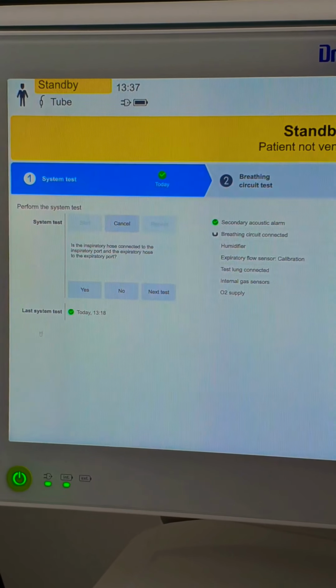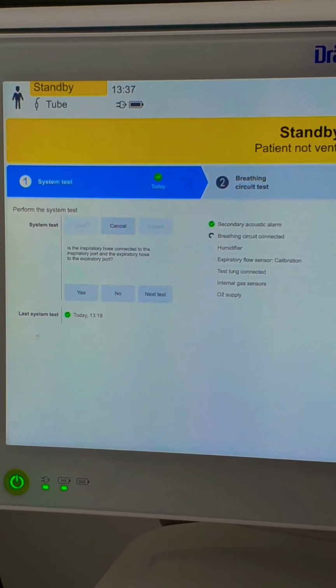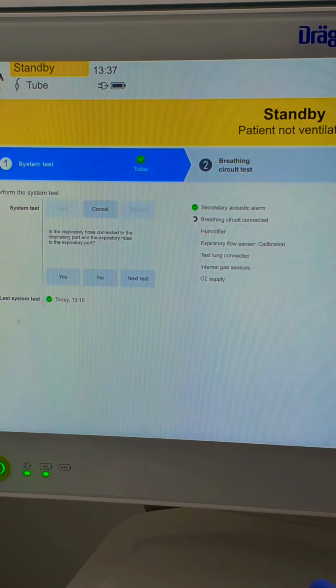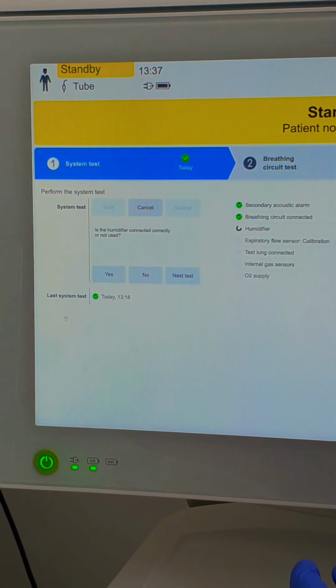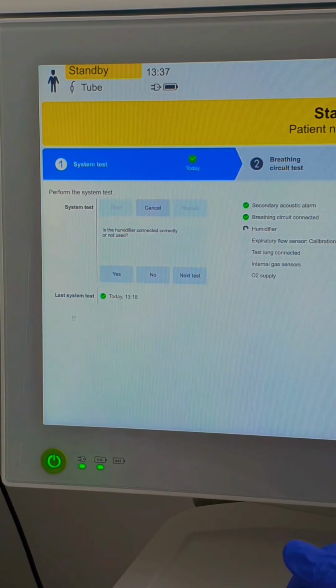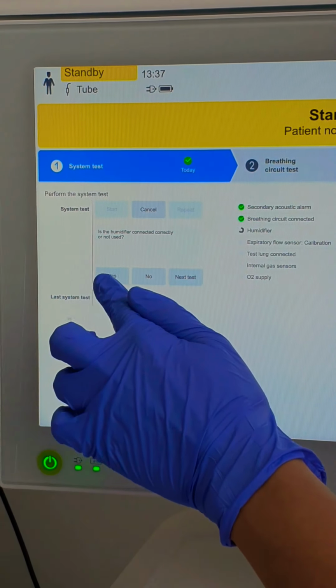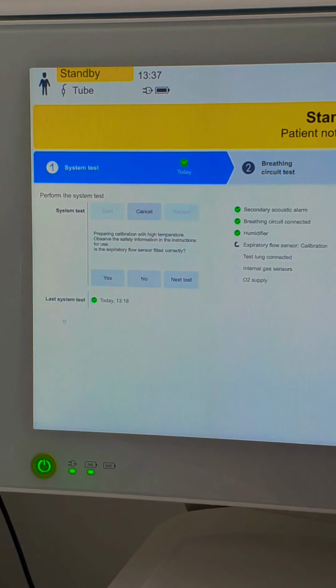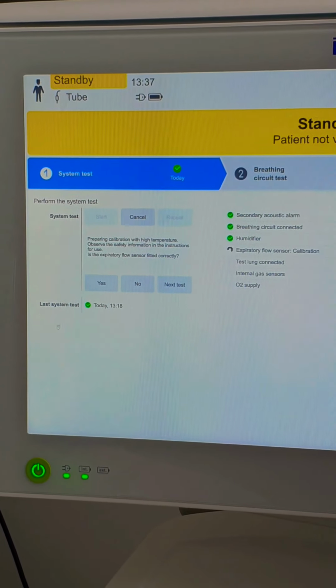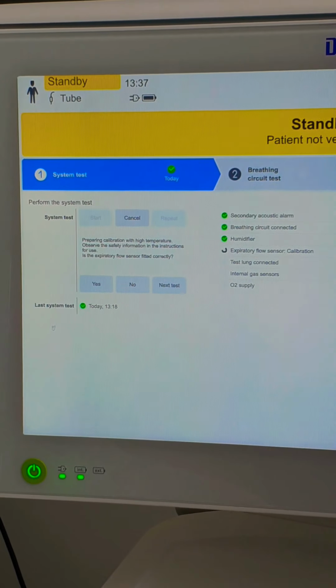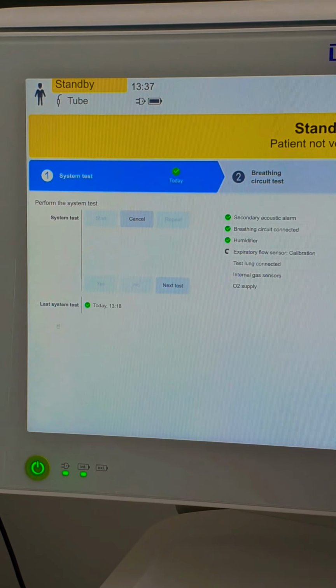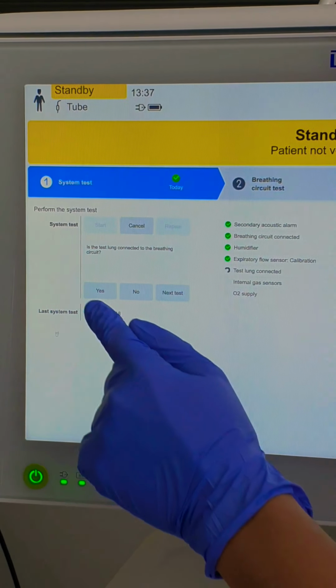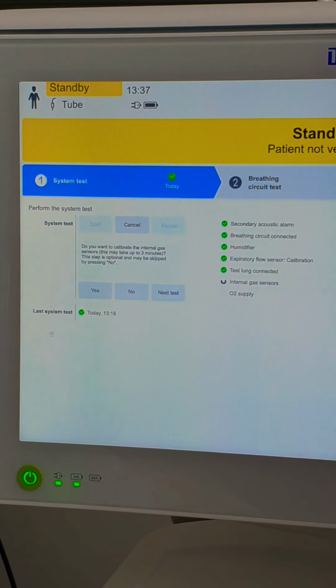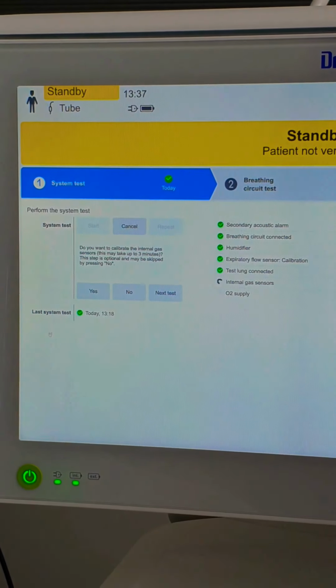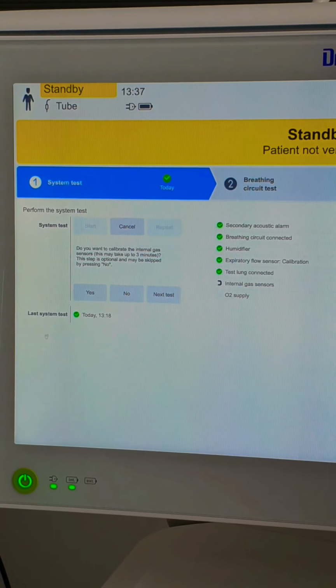The next question is, is the inspiratory hose connected to the inspiratory port, and the expiratory hose connected to your expiratory port? We tap yes. And is there a humidifier connected? Is the humidifier connected correctly or not used? We're going to press yes, since we're not using it. And in this part, preparing calibration with high temperature, is the expiratory flow sensor fitted correctly? We're going to answer yes. And is the test lung connected? That's a yes as well. In this part, it says, do you want to calibrate the internal gas sensors? It can take up to 3 minutes. You may or you may not. At this point, we will say no.